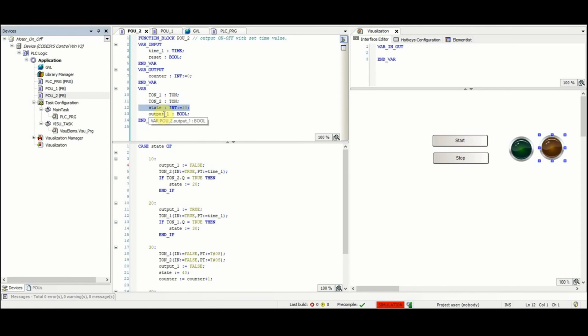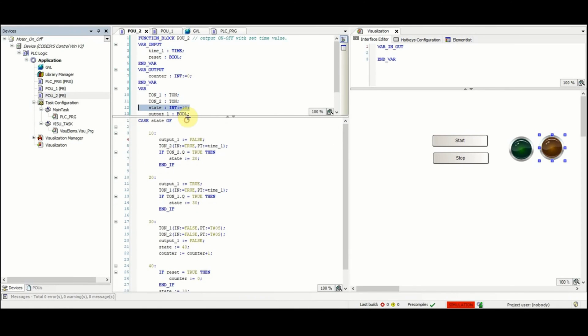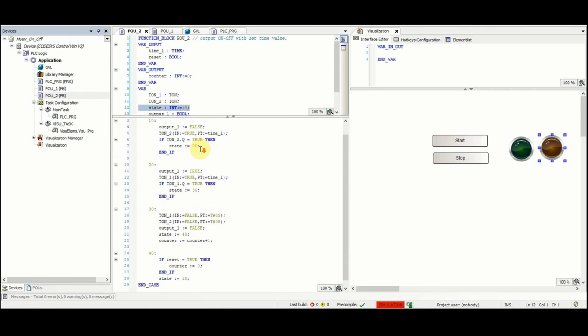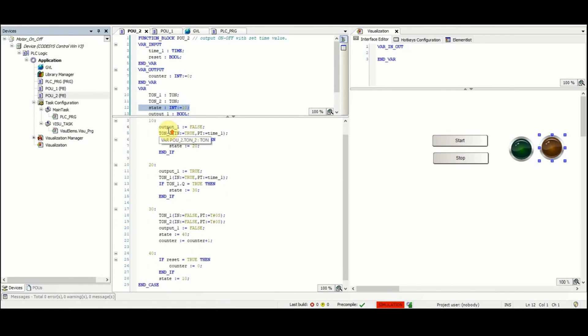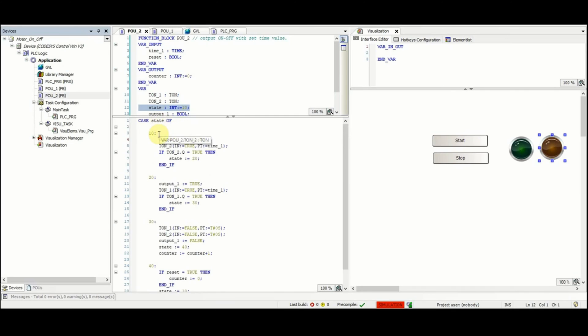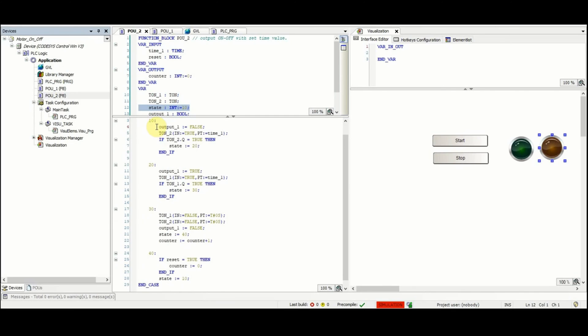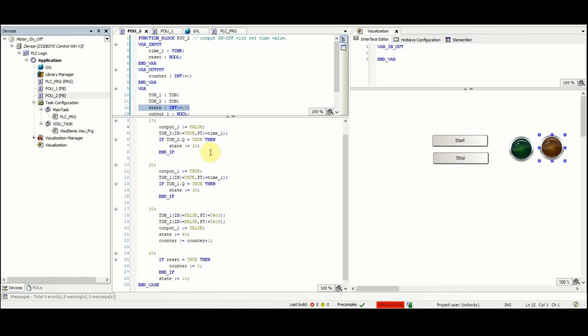We also have a case structure here for POU2. So if state is equal to 10, output_1 is set to false. On-delay timer 2, TON_2, is called with the input set to true and preset time is equal to time_1 which is the input to the POU2. When the timer is done the state will be set to 20.